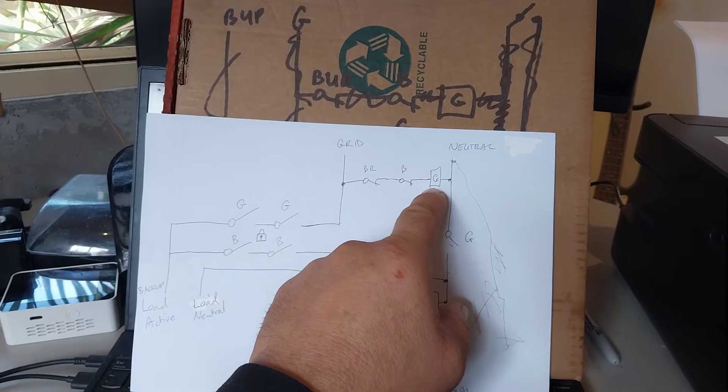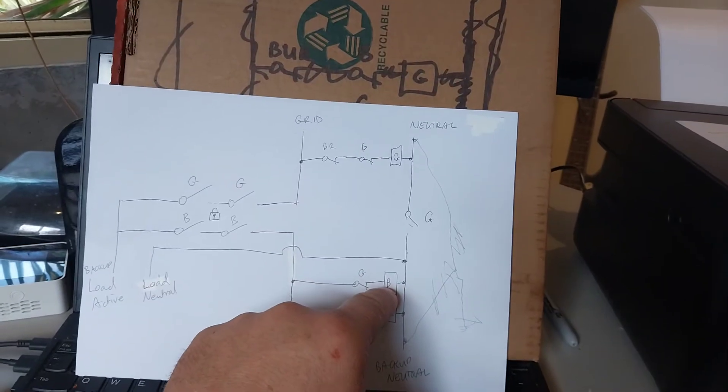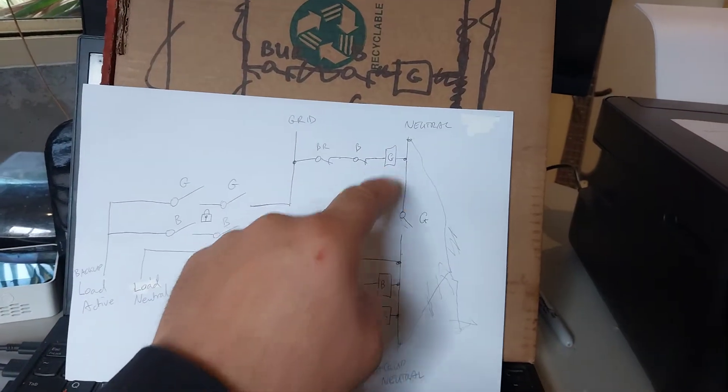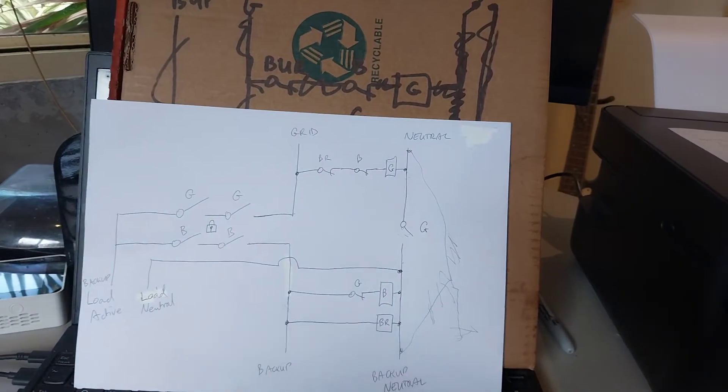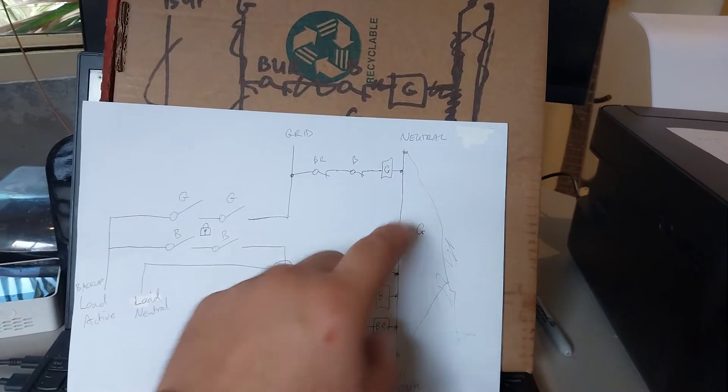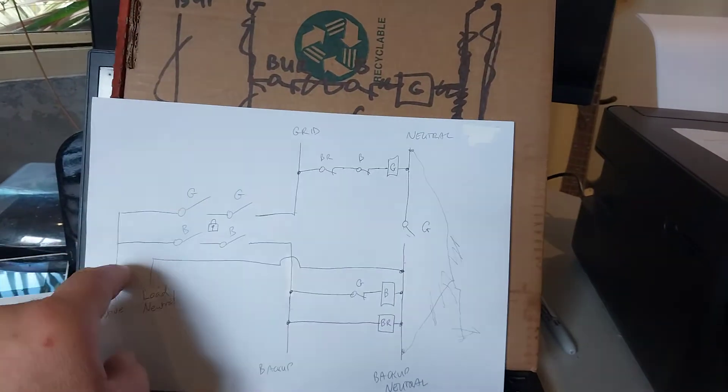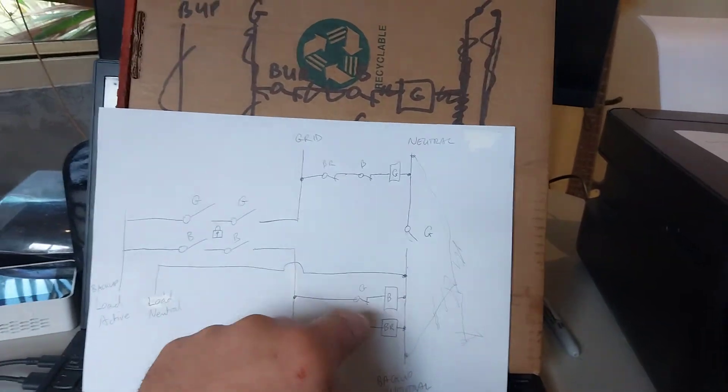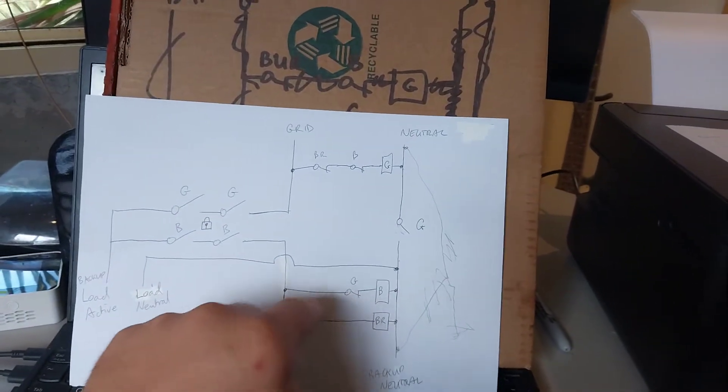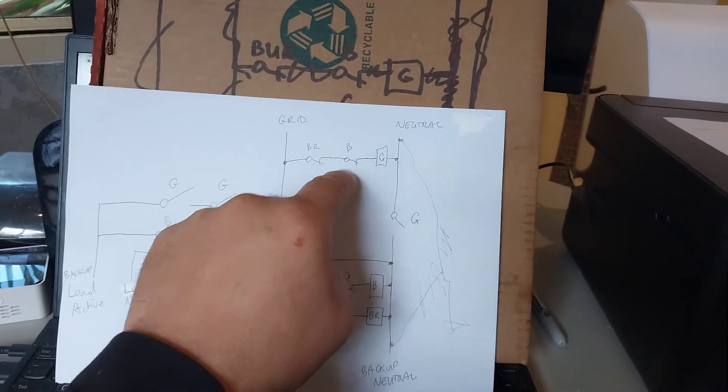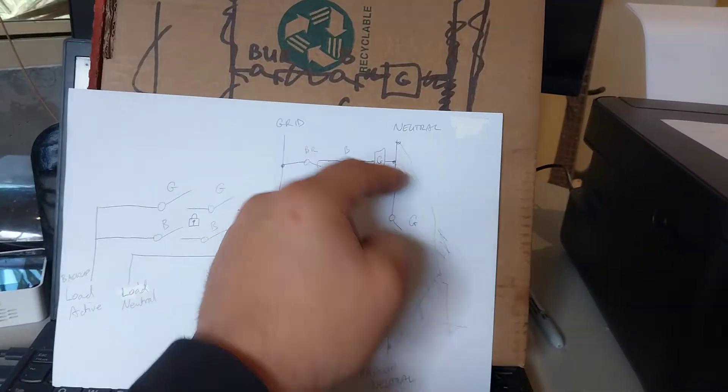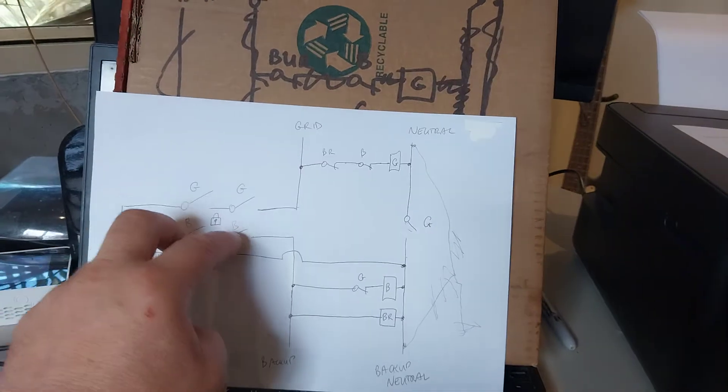Over here you can see the contactor coils, G and B. G for grid, B for backup. Obviously when this is energized and they're closed supplying power, we want this open so this cannot come on, and vice versa. This will be open when this is energized. Power cannot get to there.